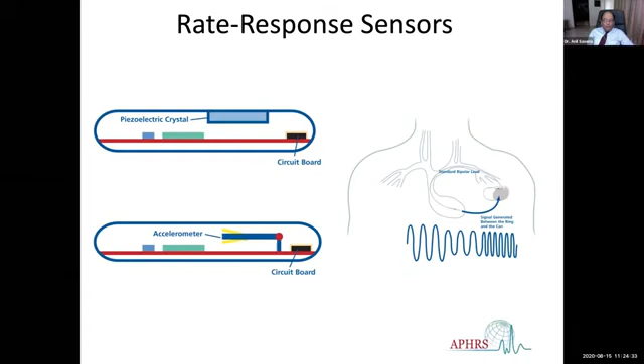And the same technology can be used by the pacemakers to count the respiratory rate. So when you exercise, the respiratory rate will go up, and the pacemaker can increase the heart rate commensurately. Many pacemakers have a blended sensor. So you have pacemakers which have minute ventilation and accelerometer combined, because the problem is that when the activity stops, the accelerometer will automatically and rapidly decrease the rate, but the minute ventilation will allow the pacemaker to continue heart rate activity.